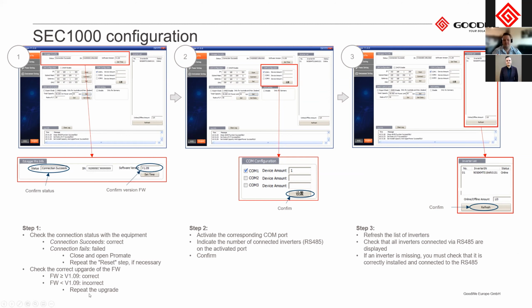So as you'll see, it just says version 1.09. So version 1.09 is the lowest firmware for us to display the metadata on the portal. I think currently we're on version 1.13. So it's always important to make sure we are on the latest version. Then you'll see we have our COM port configuration. So in the COM port configuration, you tick the COM port that you are using and you set the amount of devices it should be expecting on that COM port, and you press the set button. Don't worry, the set button is English. Just my slides are still in error. After setting that, we can hit the refresh button on the bottom side. Then it will pull up a list of all of the devices connected to our logger.